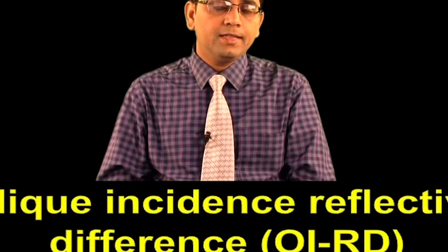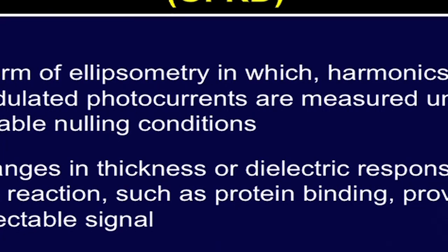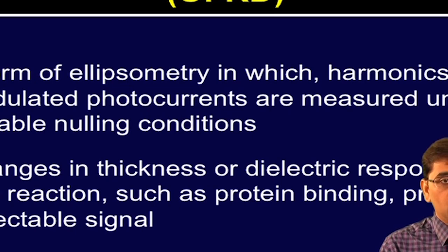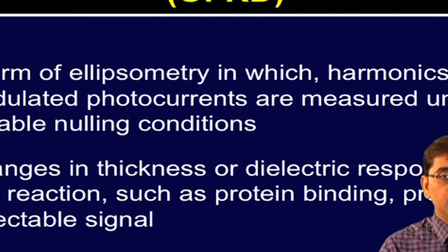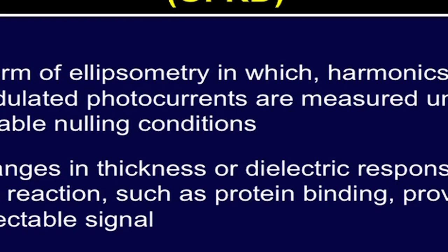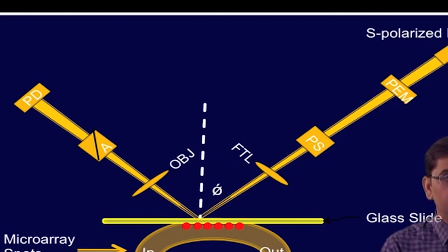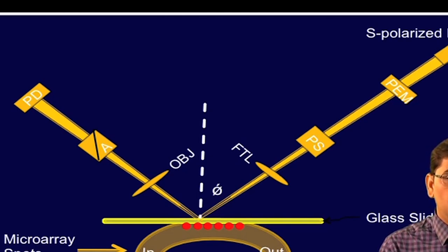Let us talk about oblique incidence reflectivity difference, or OIRD. OIRD is a form of polarization-modulated imaging ellipsometer, in which the harmonics of modulated photocurrents are measured under suitable Nulling conditions. It can be used for label-free high-throughput detection of biomolecular interactions on DNA as well as protein microarrays. In this scanning OIRD microscope, the X scan is performed by moving the sample holding stage and the Y scan is performed by a combination of a rotating mirror and theta lens.